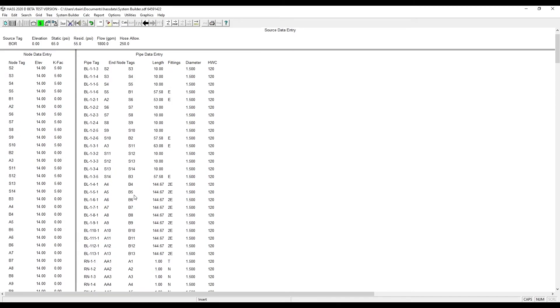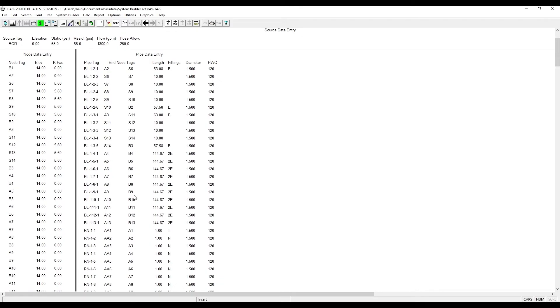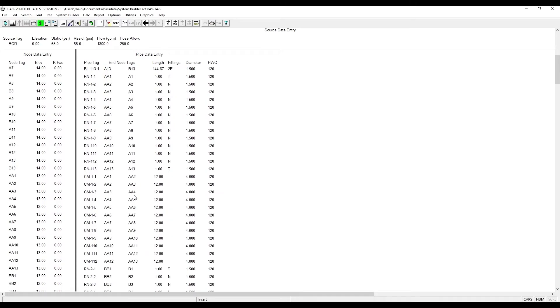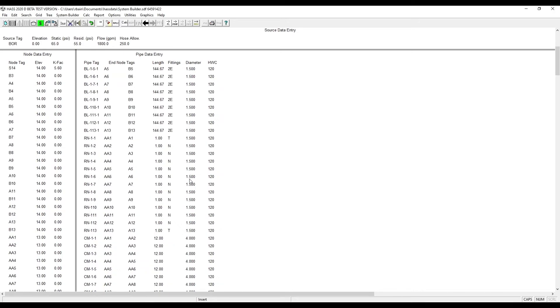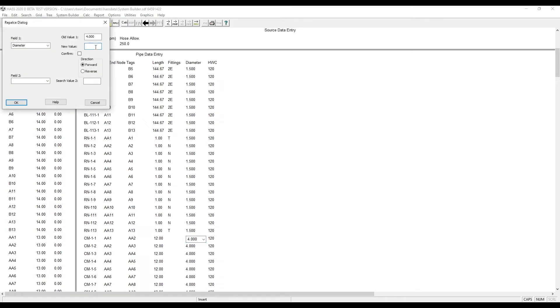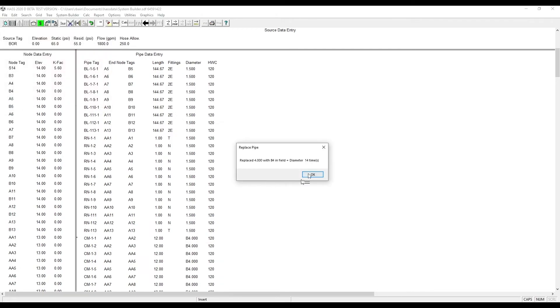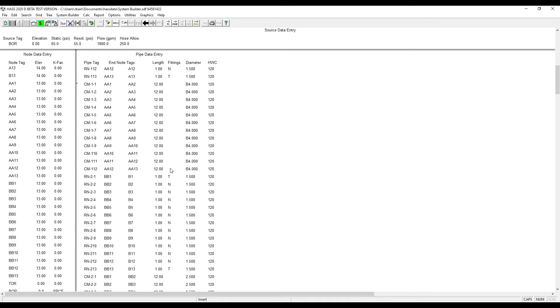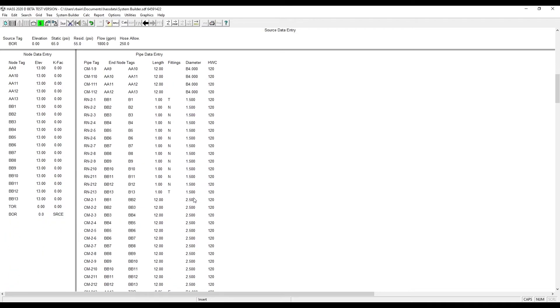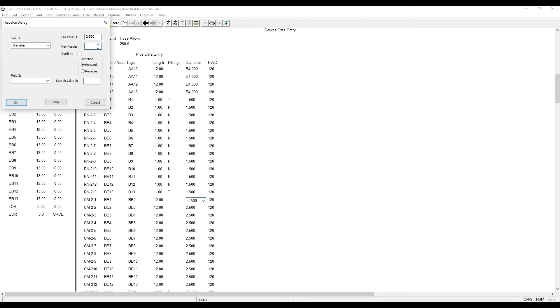As you can see here, we have a mixture of Schedule 40 and Schedule 10, but everything is entered in Schedule 40. We can go back and correct that by finding the top of where the 4 inch pipe starts, click Replace, and then B4 — the B denotes Schedule 10 in our pipe table data. Then we scroll down and do the same for the 2.5 inch pipe.